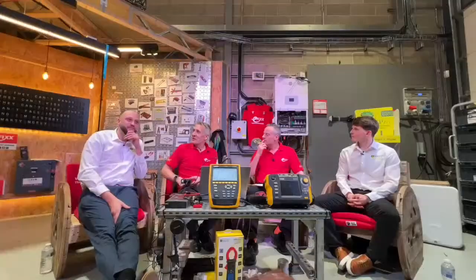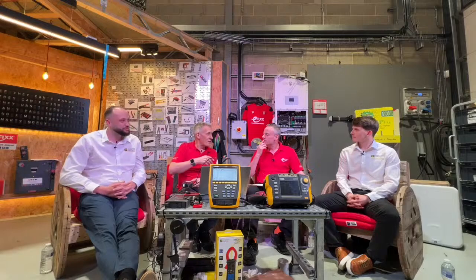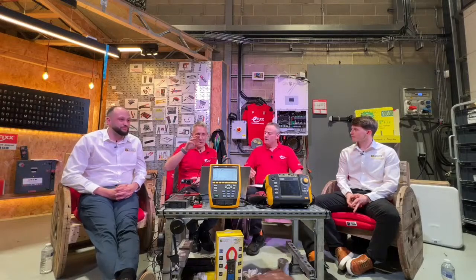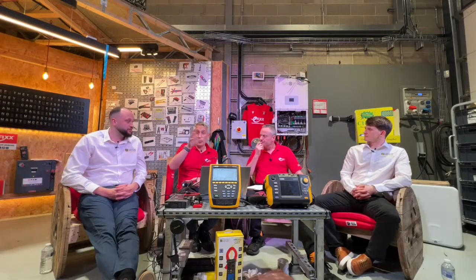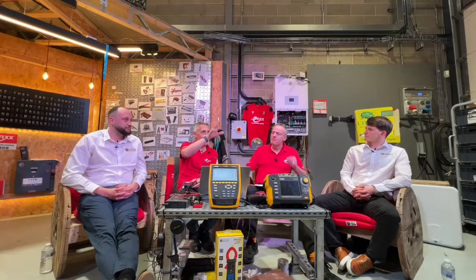So the DNO will actually stipulate that they're not going to guarantee that voltage at that point. Which I sort of thought was a bit harsh, but it's written in there. We'll dive into it in a bit, but I thought that's going to cause no end of problems because we've got PEN fault protection here. Inverters will shut down at a certain voltage, which will self-correct the problem, but a lot of the time we're seeing comments where people end up with the power problem caused by the neighbour.